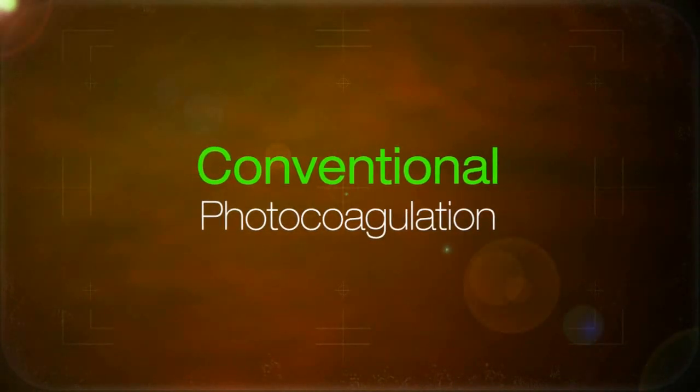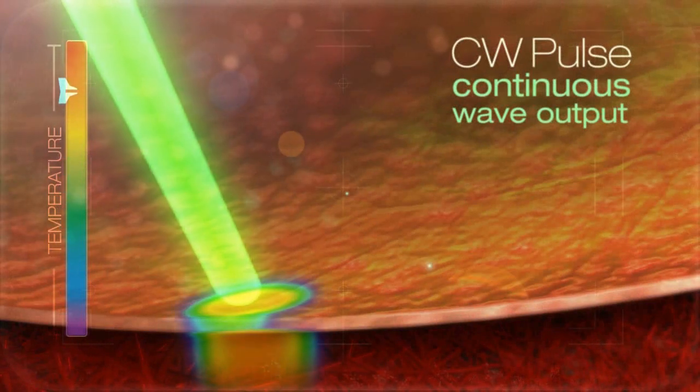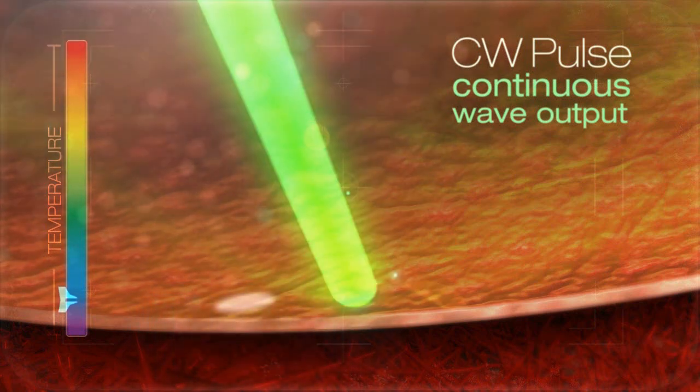In conventional photocoagulation, a CW or continuous wave output is used. Physicians adjust the laser power and exposure times, but even at the lowest levels a rapid temperature rise is seen in the target tissue.